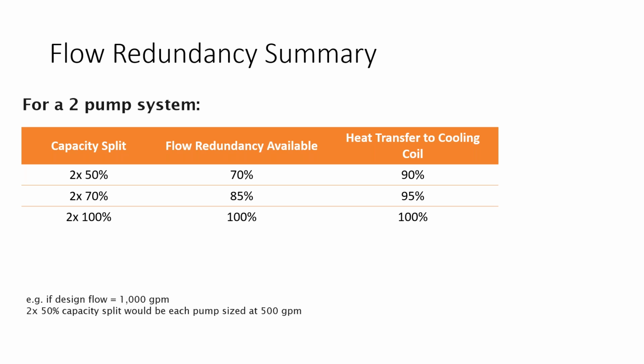So for a 2 pump system, 2 by 50 capacity split, you'll get a 70% redundancy. And look at the heat transfer. We get 90% heat transfer on that 70% flow rate. So you have to be asking yourself, how is this possible? Well, hydronics is a very forgiving technology, obviously. And the flow and the heat transfer are not a one-to-one relationship.